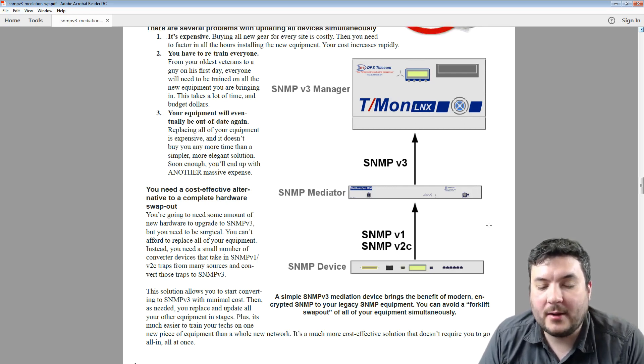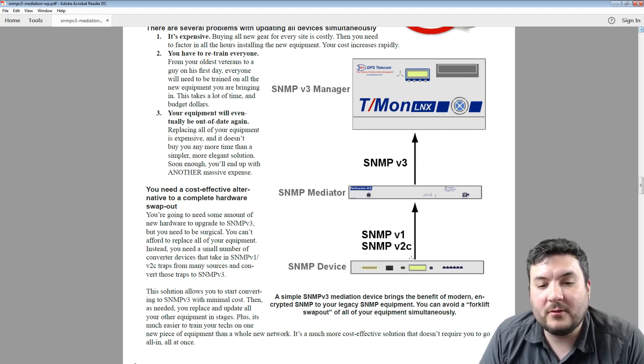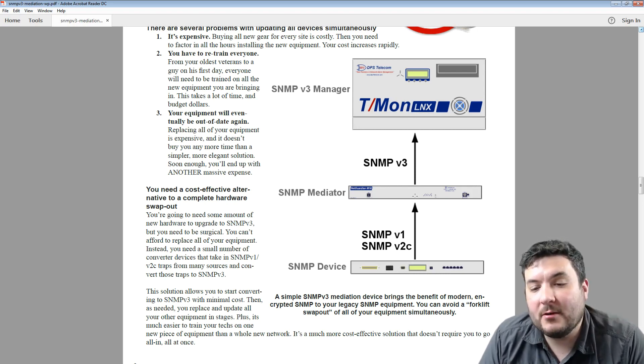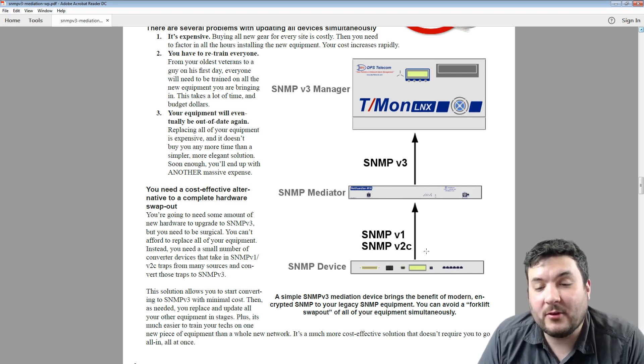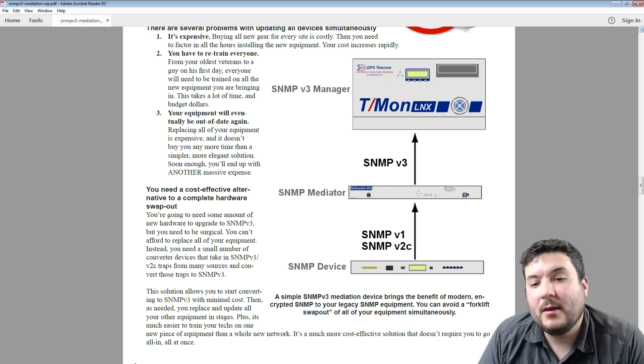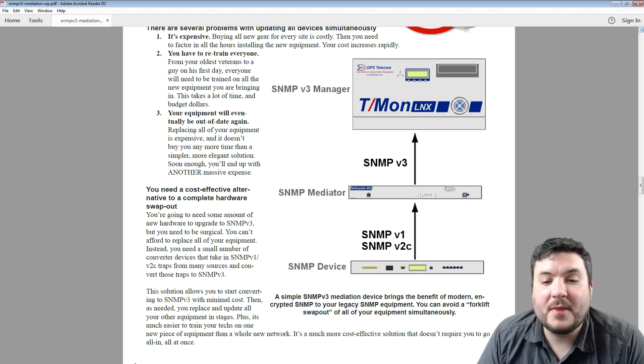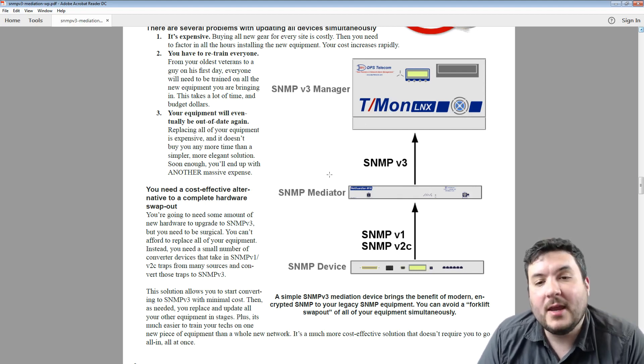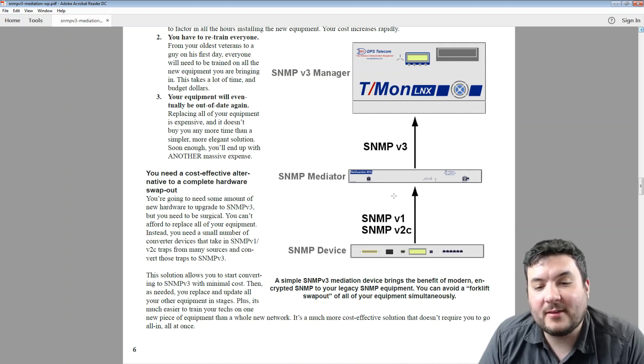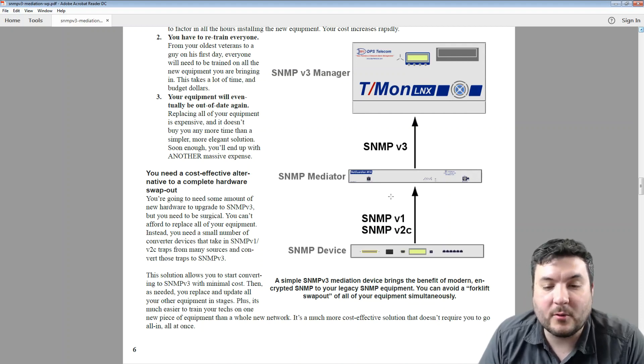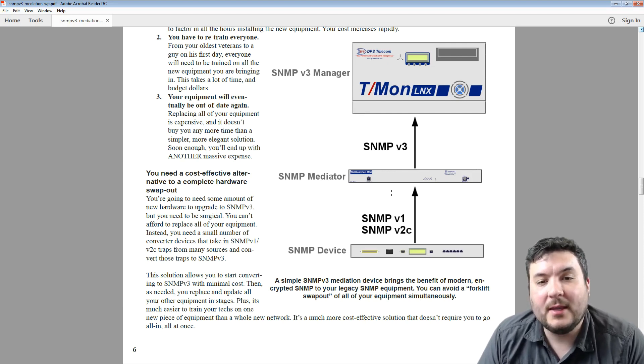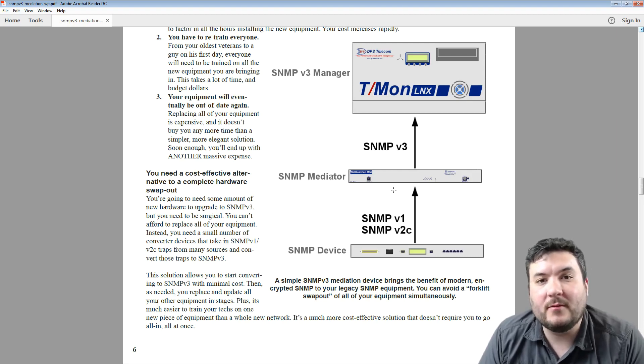The strategy that addresses this is ultimately where you take your old equipment that only supports V1 or V2C and run it into some kind of mediator device. This might have one NIC or two NICs. With two NICs, you can take in SNMP through one; the traffic doesn't route between them, but the device builds SNMP V3 secured traps and sends them up to your SNMP V3 manager. In that way, you've cut off the problem — you're not sending unencrypted SNMP across the network. There might just be an incredibly small local LAN in the room, and then when traffic leaves the building and goes across the wider network, it is secure SNMP V3.